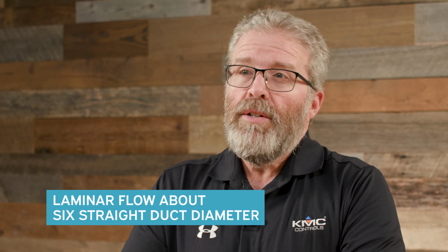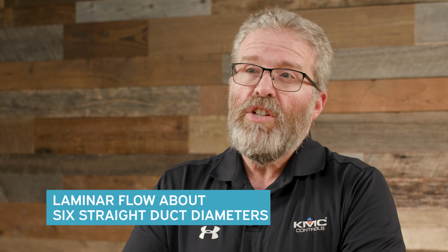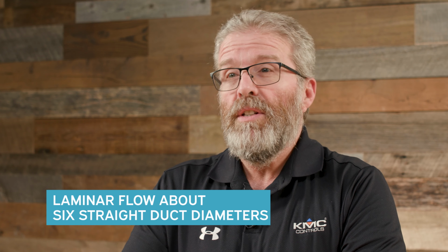The second recommendation is the pressure flow pickup tubes should be mounted in filtered air in the location of the laminar flow, which is about 6 straight duct diameters down the duct.